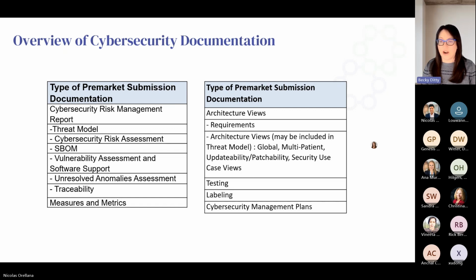Again, you're going to have your cybersecurity architecture views, and you're going to make sure that you look at it from a global view, from a multi-patient view. Some devices can be used on multiple patients. If that device gets a cybersecurity concern, how could it affect not just the patient it's being used on at that time, but anyone else that may be connected to that device at that point or in the future? Updatability and patchability. What vulnerabilities can come from your updatability and patchability process, and what's the architecture of that? And then your security use case views, which really kind of coincide with your risk assessment and the various threats and harms that you have overall to your device.